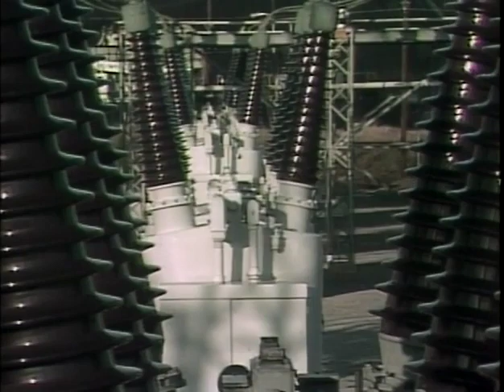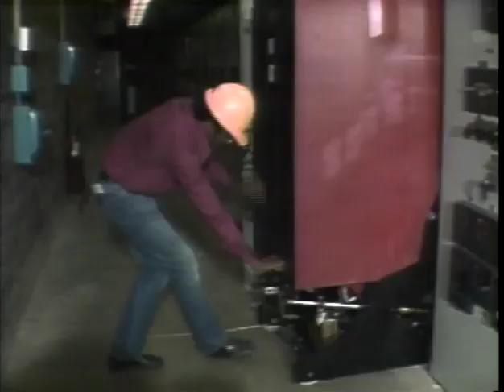And to keep you safe from the danger of arcs, circuit breakers are designed with special protective features. For example, arcs usually occur at the switch contacts where the circuit is broken. Now, that's why circuit breakers have contacts enclosed in a protective housing. This helps keep arcs contained and away from personnel and other equipment. Circuit breakers are also designed to extinguish the arcs caused by opening a circuit under load. In fact, circuit breakers are usually classified according to the method they use to extinguish arcs. Some circuit breakers use air to extinguish arcs, some use gas, and some use oil. Let's see how each of these breakers works.